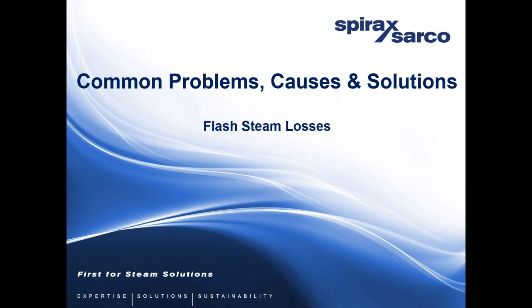It sounds like the buildup of carbonic acid in your system. So you have air entering your steam system. This could be during shutdown, so that your gaskets or air vents or vacuum breakers are allowing air into the system, forming carbonic acid, and that's sitting there in the traps until the system is fired up properly. It could be water hammer causing damage to the ball, so it's no longer effective, or it could be particulates in the steam trap getting caught on the valve seats, so that they're no longer closing properly. With the excessive corrosion, I would say that would more likely be either the carryover of chemicals or the formation of carbonic acid in your system.